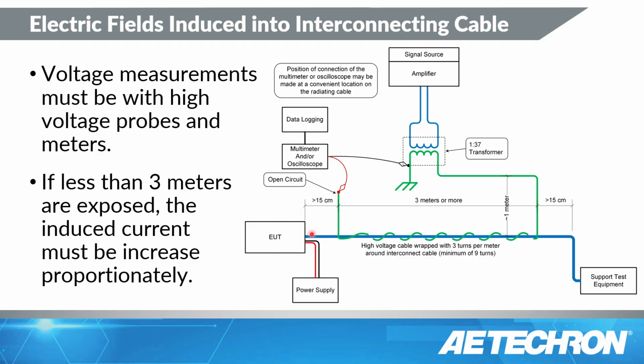Make sure you have some space here. 15 centimeters on this side. And mainly that is to assure that you're not coupling this field directly into the equipment or directly into the connector. That's the reason why they want some of the spacing. This side is done because, well, maybe you have support equipment that's somewhat sensitive. So we want to make sure that we're not making the equipment susceptible because of the test that we're performing.